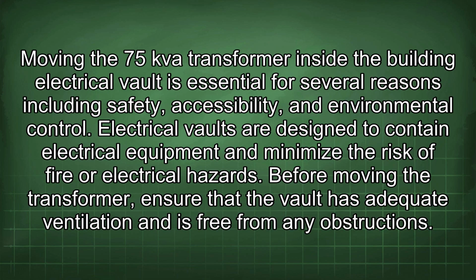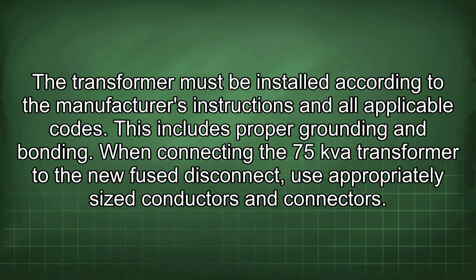Moving the 75 kVA transformer inside the building electrical vault is essential for several reasons including safety, accessibility, and environmental control. Electrical vaults are designed to contain electrical equipment and minimize the risk of fire or electrical hazards. Before moving the transformer, ensure that the vault has adequate ventilation and is free from any obstructions. The transformer must be installed according to the manufacturer's instructions and all applicable codes. This includes proper grounding and bonding.